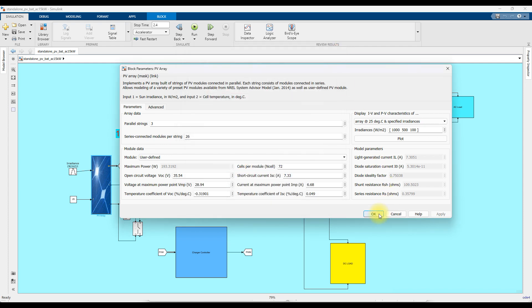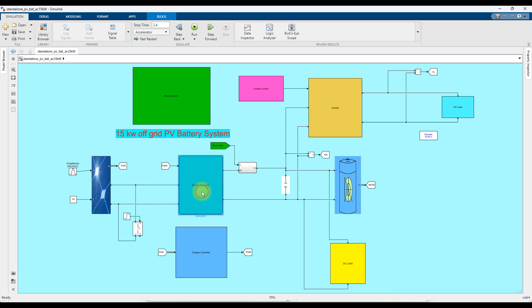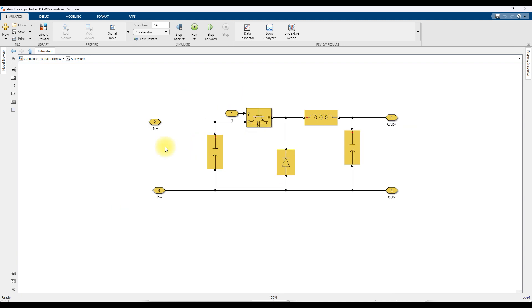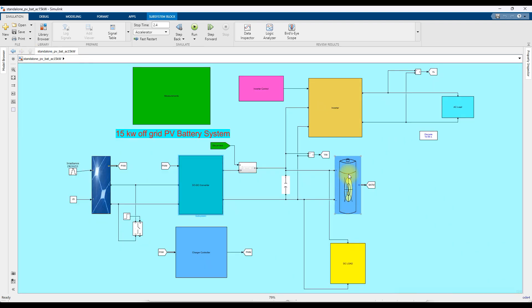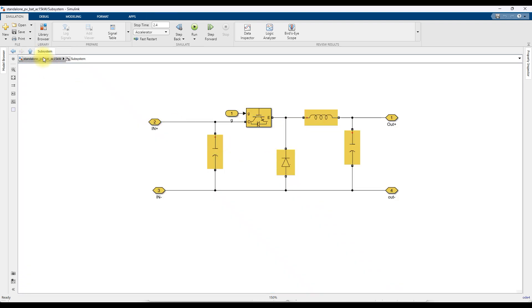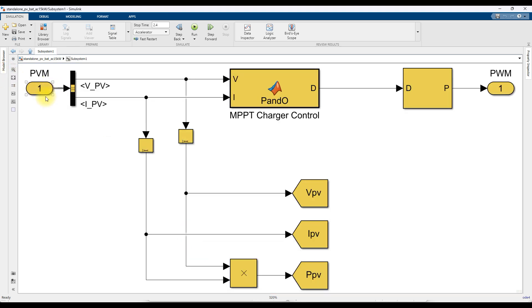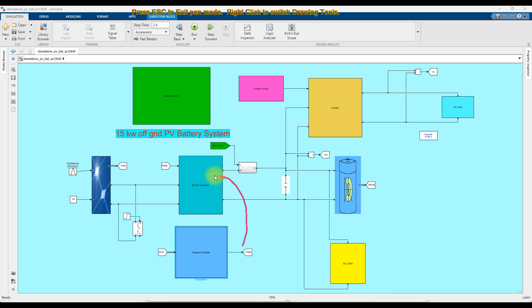This PV array is connected to the battery via a DC-DC converter. We are using a buck converter to step down the voltage from 750 volts to the battery's required voltage. The buck converter is controlled by means of a charge controller. The charge controller receives the PV voltage and current measurements, and based on those, generates a duty cycle. That duty cycle is processed via a PWM generator, which controls the buck converter.